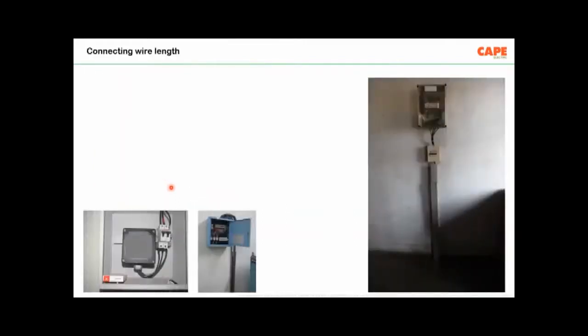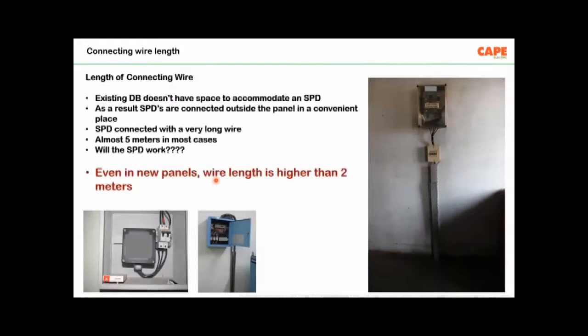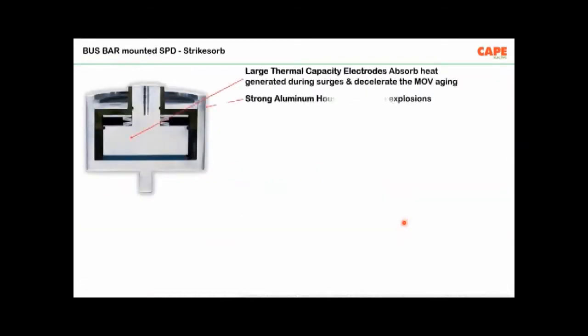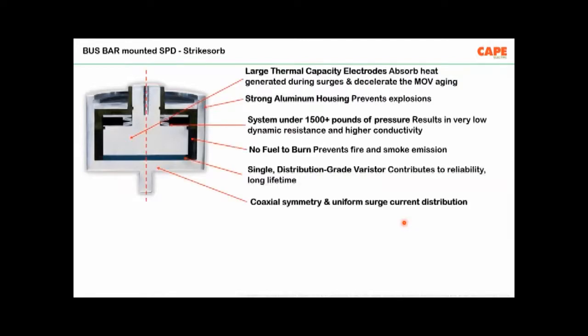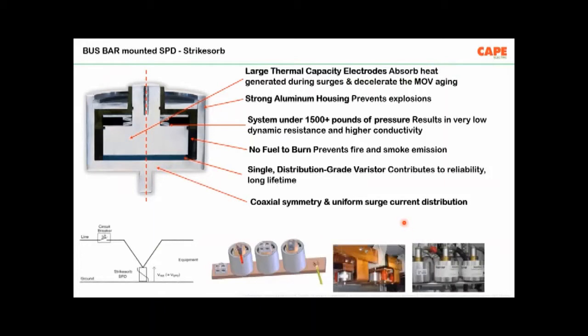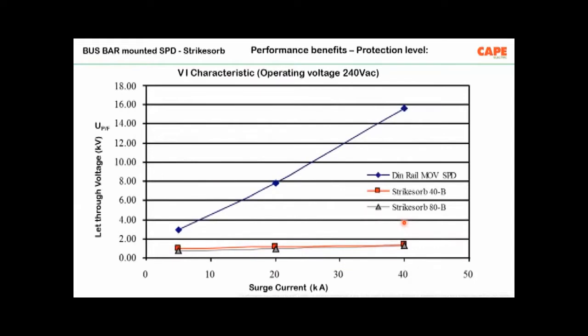But unfortunately, if we look at 100 SPD installations in our country, almost 80 SPDs are installed in this fashion. The wire length recommended is 250 millimeter, but more than 2 meters are used. As a result, in most cases, SPDs are just like decoration. It won't work. For this particular purpose, you must use special SPDs like the bus bar mounted SPDs. The advantage of these bus bar mounted SPDs is you are directly mounting on the bus bar. As a result, the voltage drop due to line length has been nullified. There is no line length applicable.